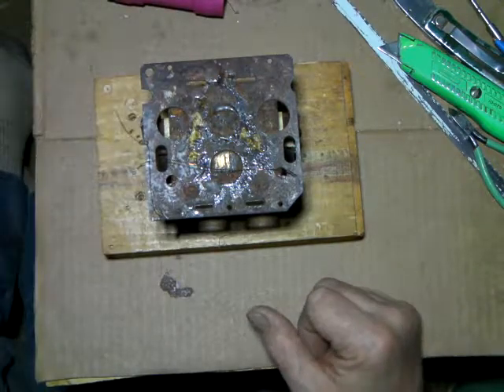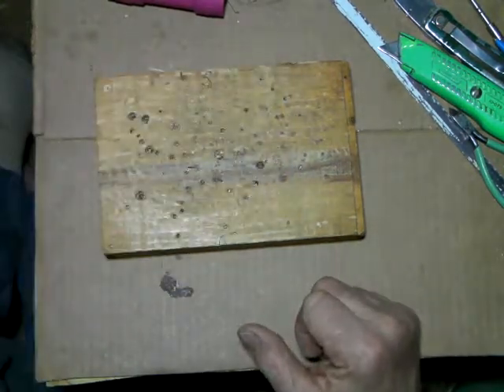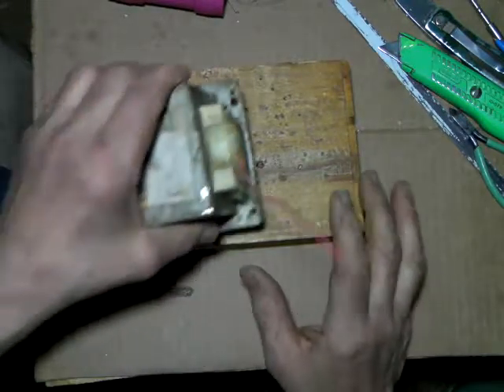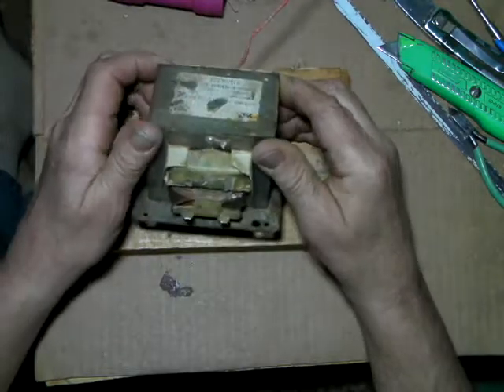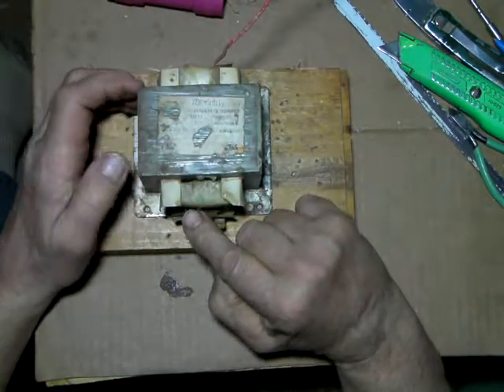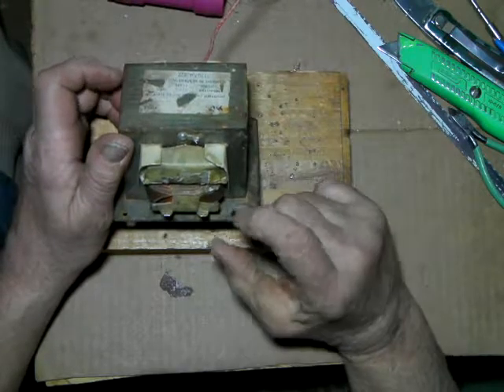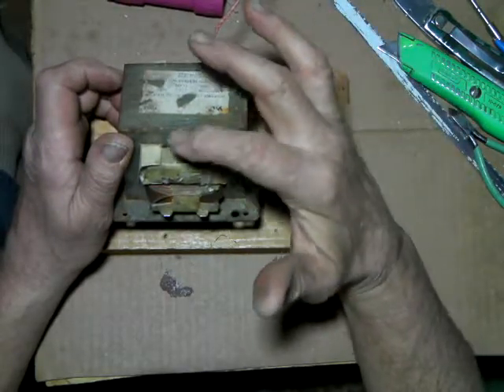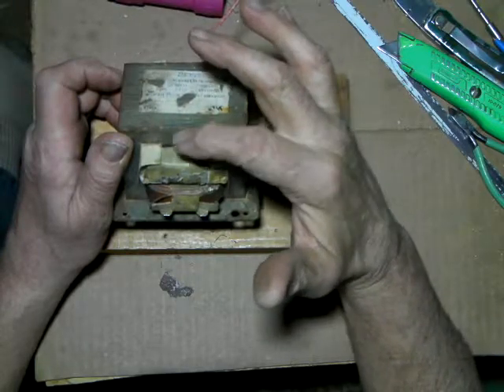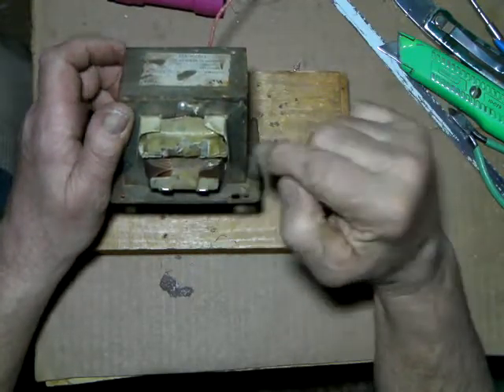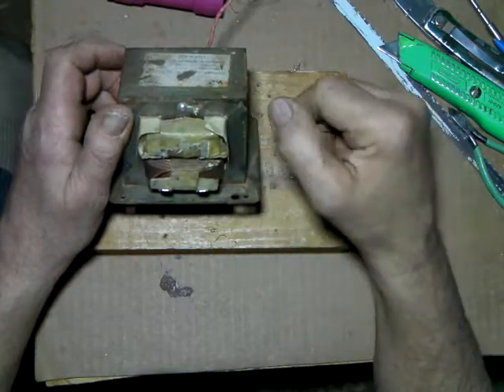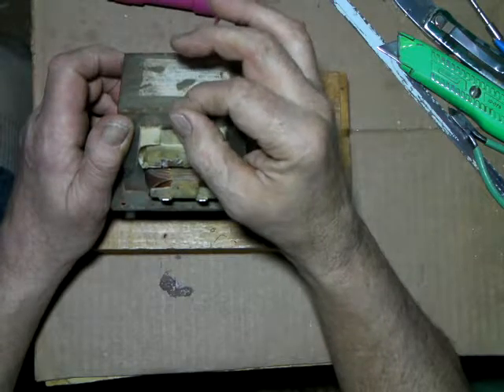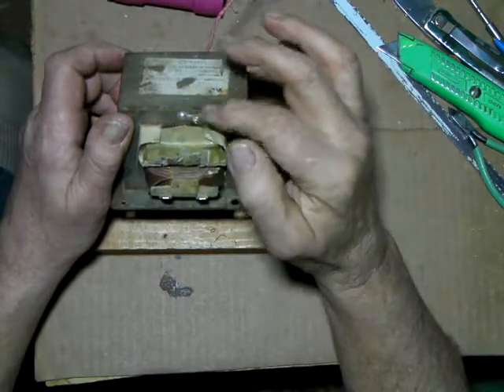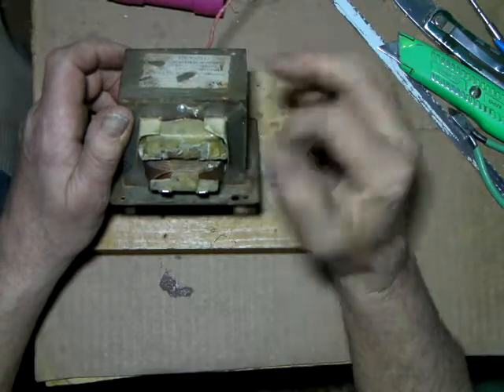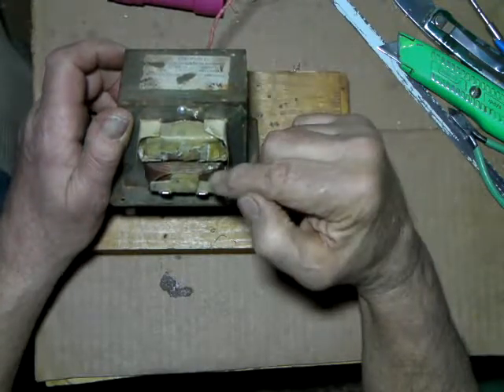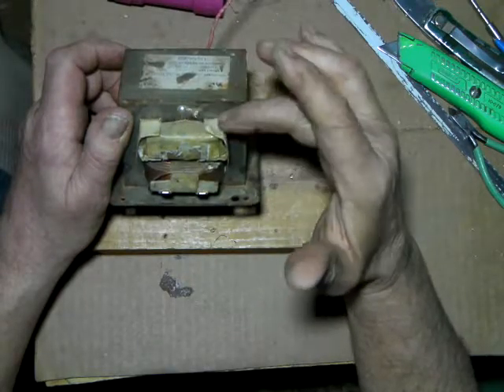A couple other things I'd like to talk about on these transformers. I've seen recently, I've hit a few of these, that the wire is made of aluminum. If you run up on one of these, try your best not to disturb this wire. Trying to do the drill thing to remove turns isn't going to work, because you'll never be able to reconnect to that aluminum. It just won't work, it's fragile, it'll break off. The best thing to do with these transformers is simply take the shunts out and leave it as is.